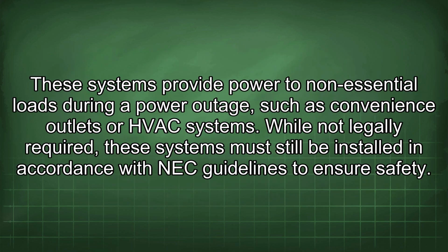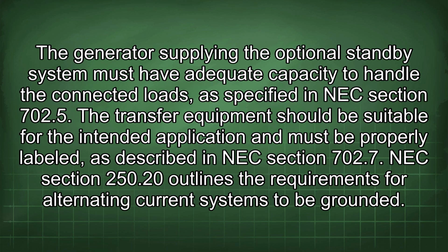These systems provide power to non-essential loads during a power outage, such as convenience outlets or HVAC systems. While not legally required, these systems must still be installed in accordance with NEC guidelines to ensure safety. The generator supplying the optional standby system must have adequate capacity to handle the connected loads, as specified in NEC section 702.5. The transfer equipment should be suitable for the intended application and must be properly labeled, as described in NEC section 702.7. NEC section 250.20 outlines the requirements for alternating current systems to be grounded.